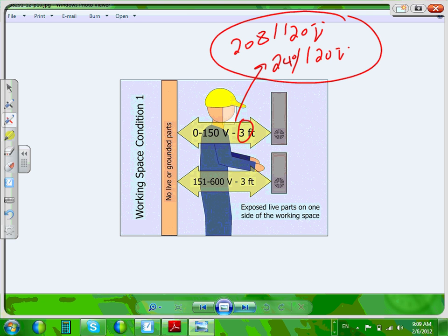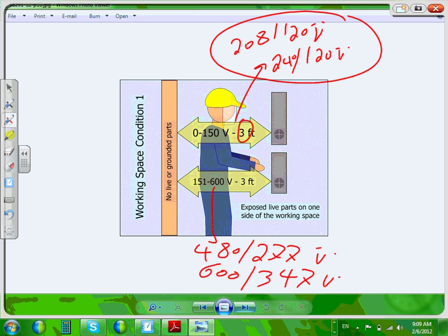If you go to a system, we talked about this one, guys, 480/277 or 600/347 or something like this, these 2 systems, then you also need to go 3 feet. All of them are 3 feet. All of them are 3 feet. Any question, guys, about this? So for condition 1, if there are no live or no grounded parts, okay, 3 feet.